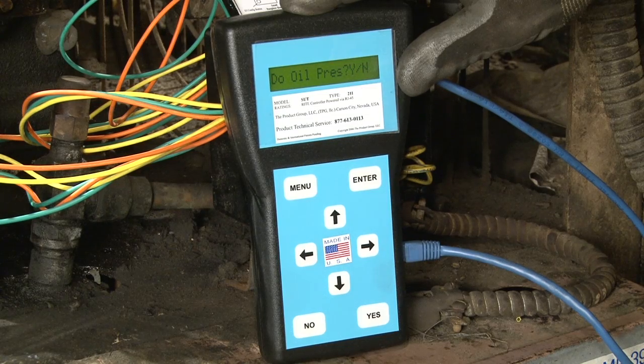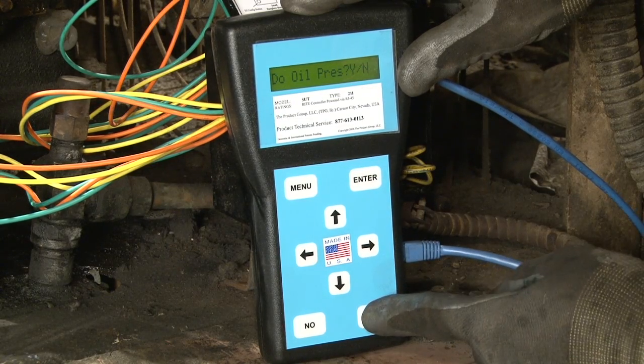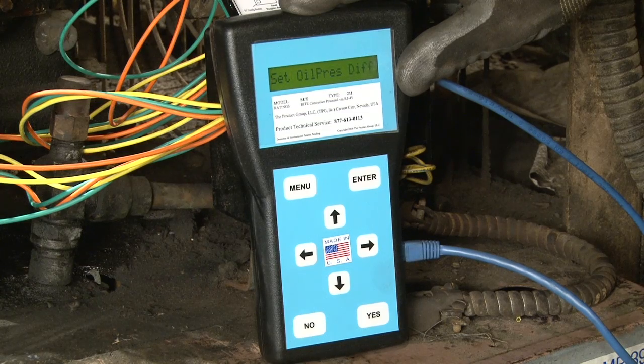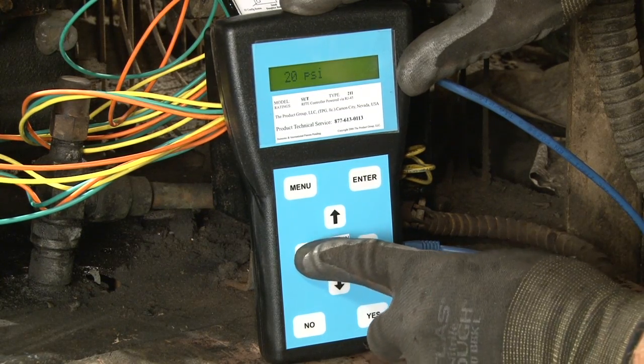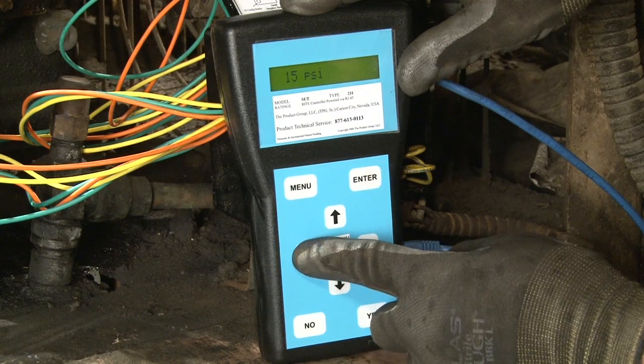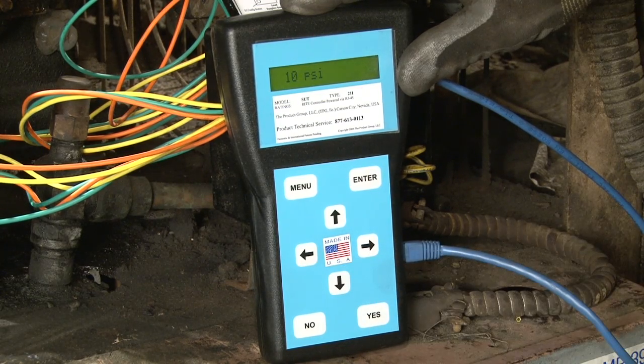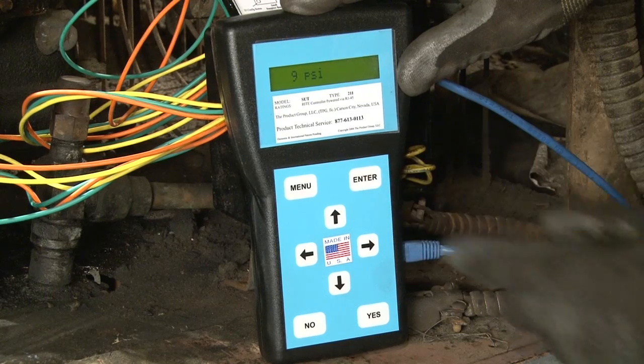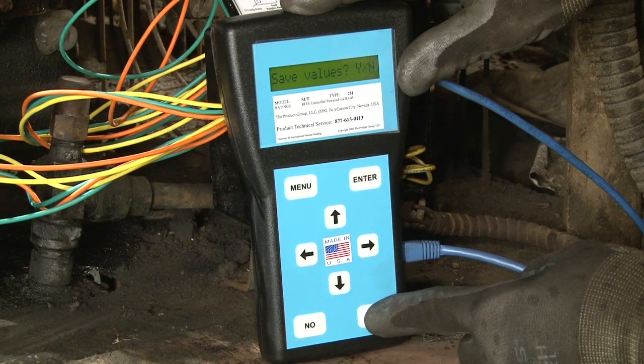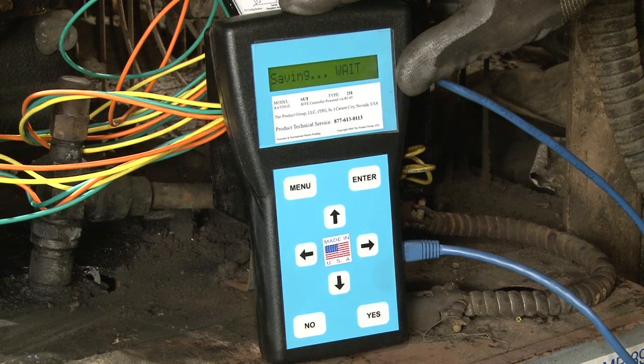It now asks if we'd like to do oil pressure. We answer by pressing the yes button. This is a Copeland compressor, and we therefore set the differential set point of the oil to be 9 psi as instructed by Copeland. We press enter. It asks us if we'd like to save the values. We say yes. The waiting process while these set points are being written to the processor chip takes approximately 20 to 30 seconds. When completed, it will tell us it was successful, and will then move back to the main menu screen.